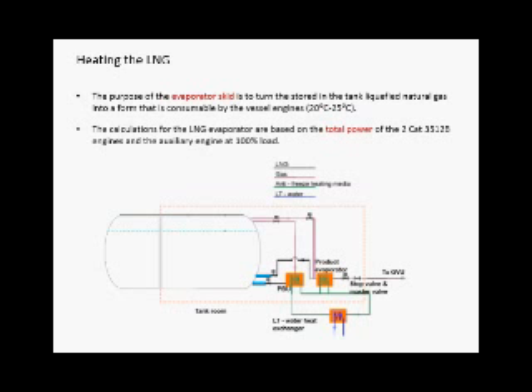Actually, another unit is used that takes LNG from the tank and evaporates it. The boil-off gas increases the pressure in this space. Based on a second line, this boil-off gas can be heated, and the pressure can provide the required mass flow rate to feed the engines with natural gas. So apart from the design, other control problems in this specific case exist and need to be taken into account.